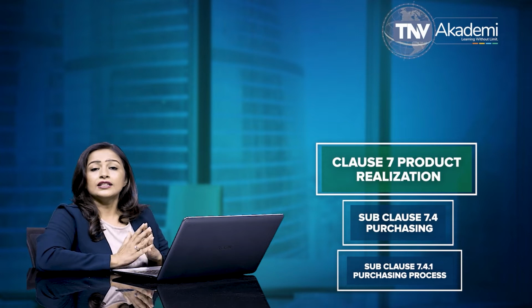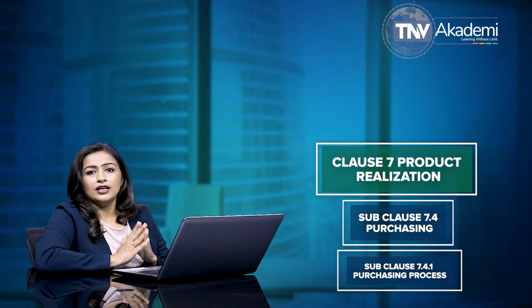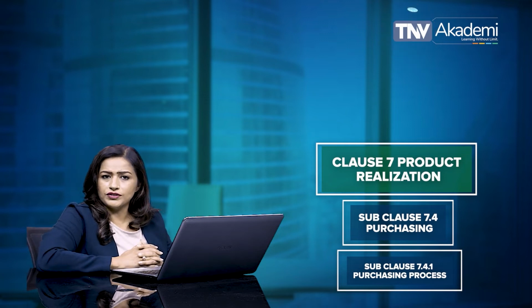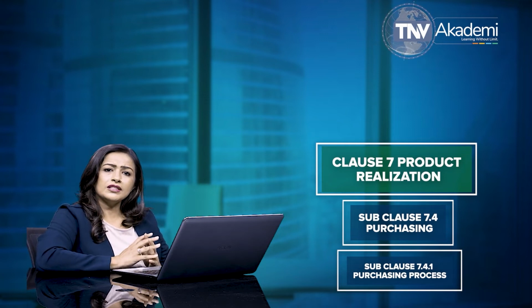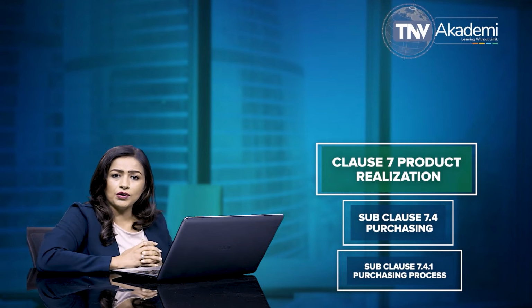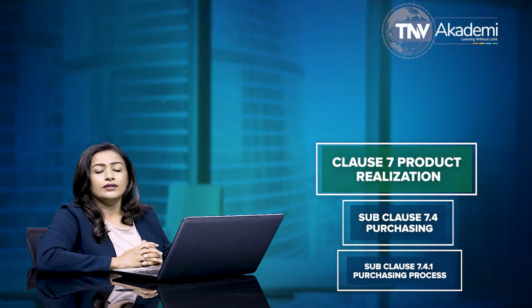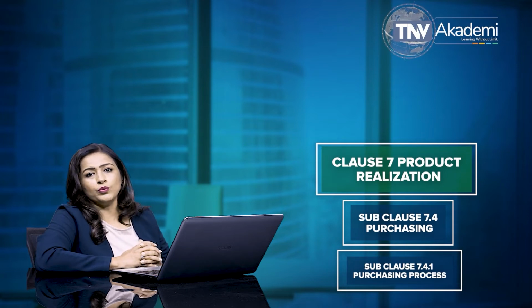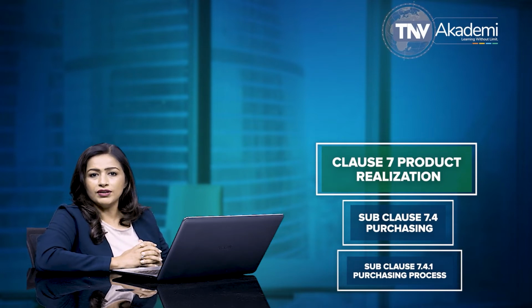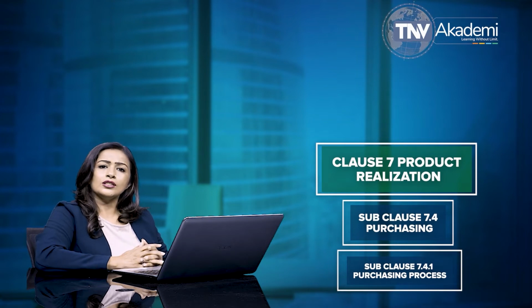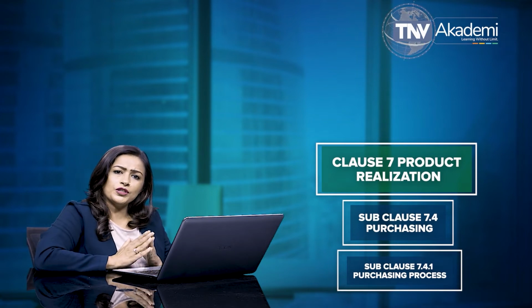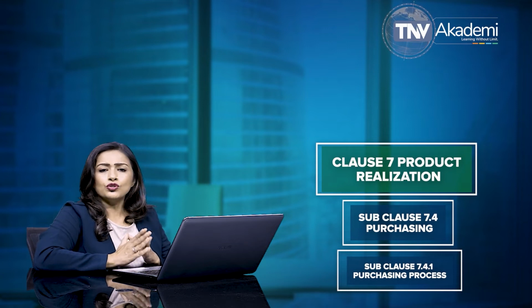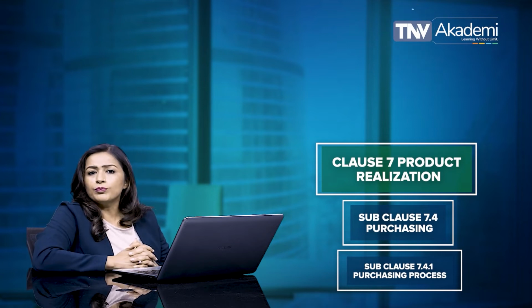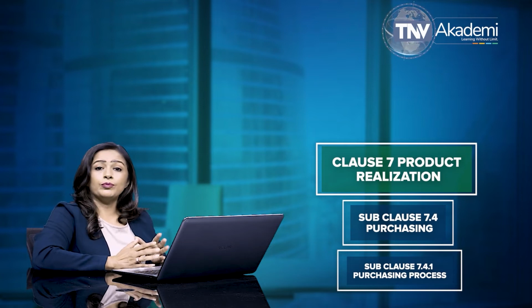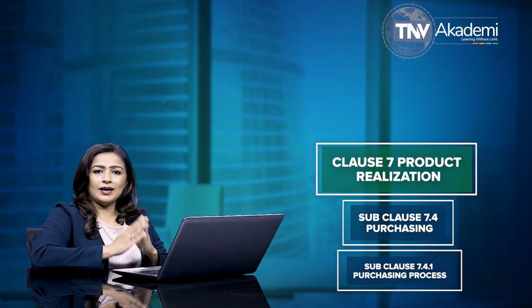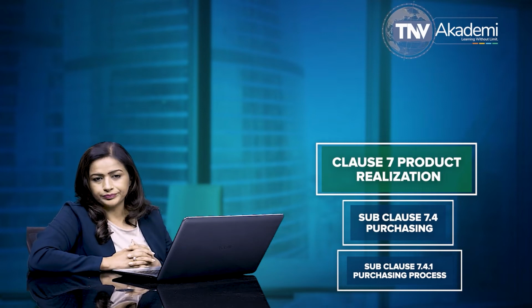Subclause says that the organization is required to plan the monitoring and re-evaluation of suppliers. Supplier performance in meeting requirements for the purchased product must be monitored. The results of the monitoring must provide an input into the supplier re-evaluation process. This clause specifies that non-fulfillment of purchasing requirements are required to be addressed with the supplier proportionate to the risk associated with the purchased product and compliance with applicable regulatory requirements.